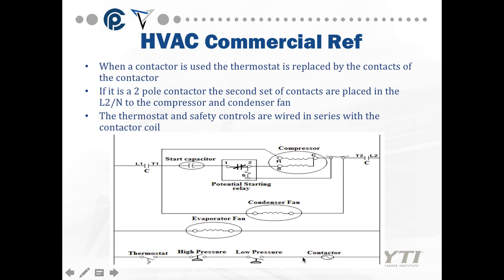The thermostat, high-pressure, and low-pressure feed into the contactor. This is for a much heavier system where the thermostat cannot handle the amperage demands of the compressor and condenser fan. The thermostat controls everything through the contactor. This is the type of diagram we want to see drawn for class assignments, and we want to see everything labeled.